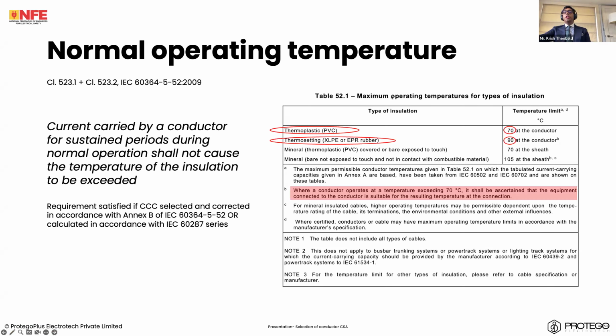Now, there are two important types of insulation that we generally use on cables in low voltage electrical installations. There are four listed in this, but most of the time you use either thermoplastic or thermosetting. Thermoplastic has a 70 degree conductor temperature, and thermosetting has a 90 degree conductor temperature. Again, remember, this is not to do with the actual copper or aluminium conductor. This is to do with the temperature the insulation can handle.